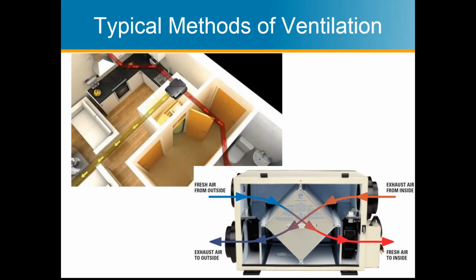And pictures of balanced HRV systems. So the picture on the lower right is an HRV, and this is just kind of how the inside of the box looks. The fresh air from outside is coming in cool. It warms up through this heat exchanger box in the middle, and it comes into the house warmer. So that's the principle of them. The downside of these systems is they're much more expensive to install. Typical install on a single-family home would be $1,800 to $3,000 probably.